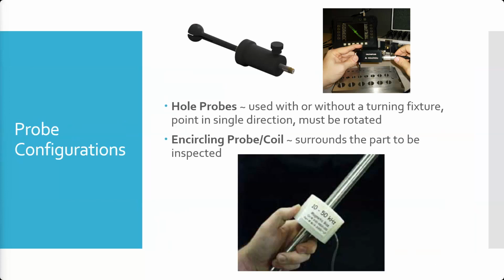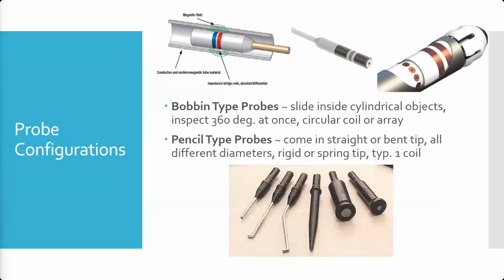You run this rod through the middle. As long as the rod is homogeneous, the inductive reactance and the impedance of the coil isn't going to change. But if you have some kind of a flaw or discontinuity or a crack, if that passes through the coil, you're going to get that change in impedance that your tester is going to pick up. And you'll be able to see that. So that's called an encircling probe.